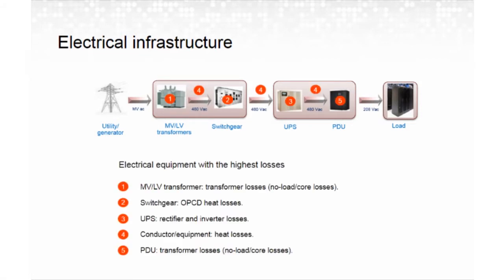So when you look at that infrastructure, there are really five components that have the highest losses. You look at the medium voltage to low voltage transformer. So there are transformer losses, no load losses, core losses. The switchgear itself has heat losses, and the protection unit has some heat losses. The UPS has a rectifier that goes from AC to DC, so there are losses there, and then from DC back to AC in the inverter, so there are additional losses.